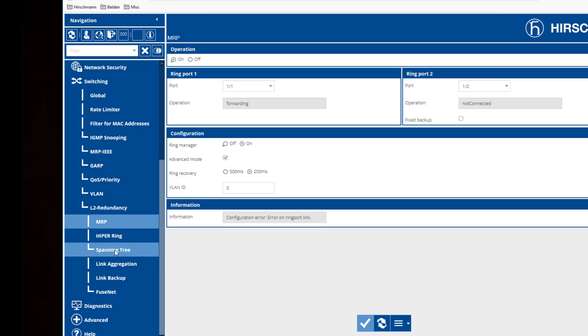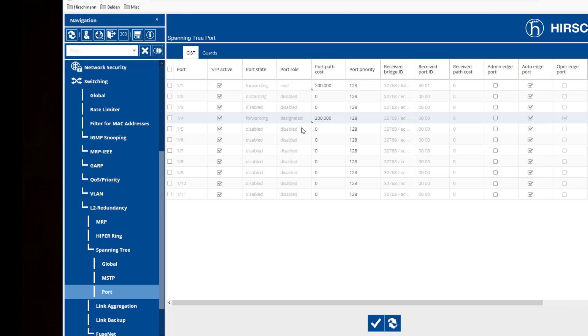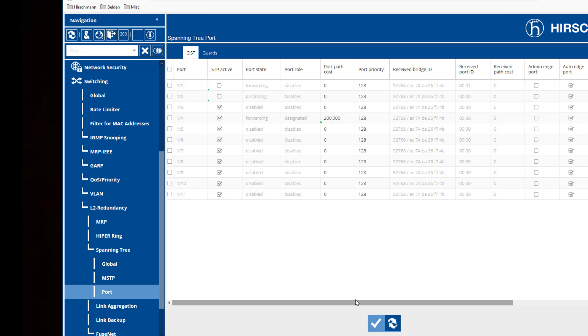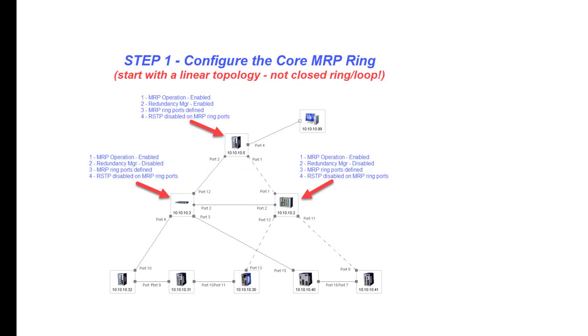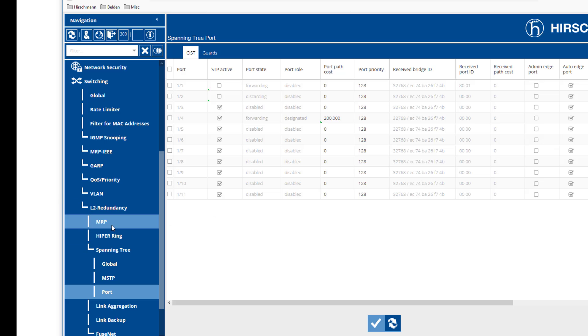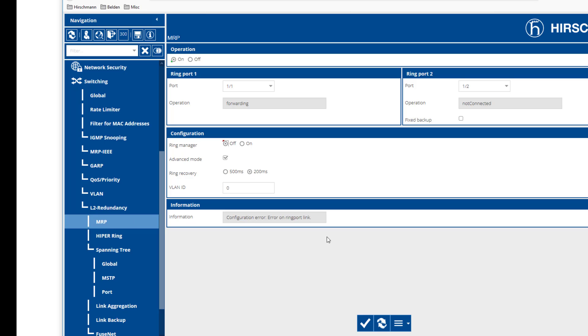We will then hit write. Then we're going to go to spanning tree, and we're going to disable spanning tree on our ring ports. In this case, our ring ports are ports 1 and 2, and we will disable them there. That pretty much covers what needs to be done in this switch. We will then go into the other two switches and replicate the settings, defining our MRP core ring ports. The only difference is that in those two switches we will not enable the ring manager.